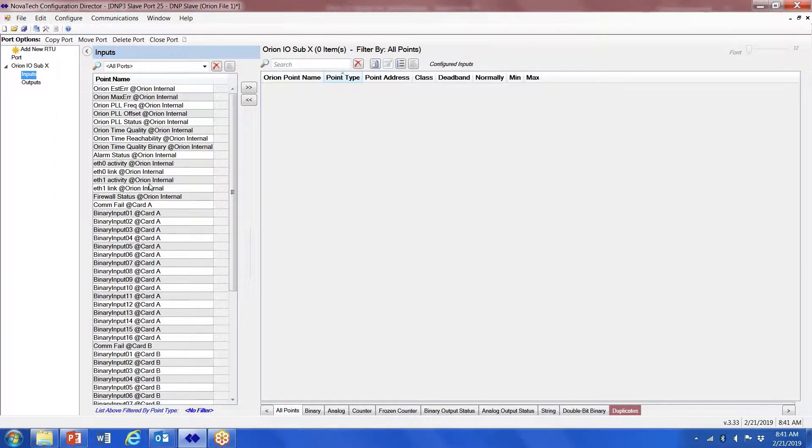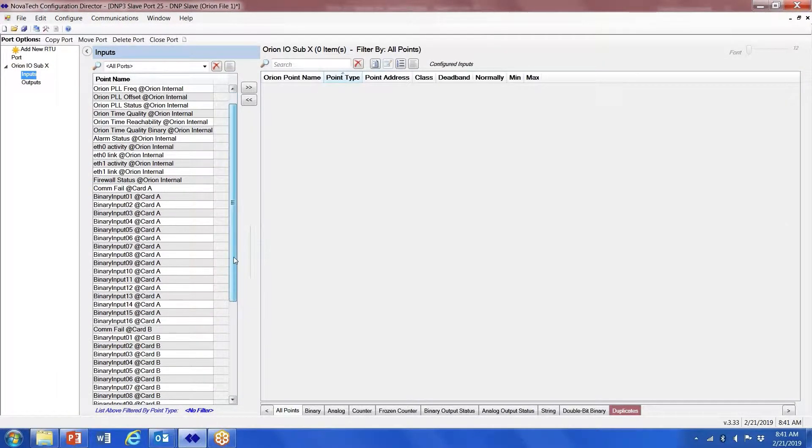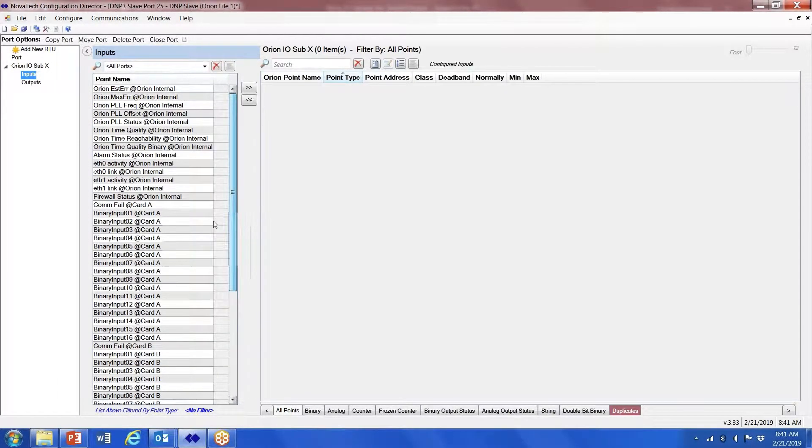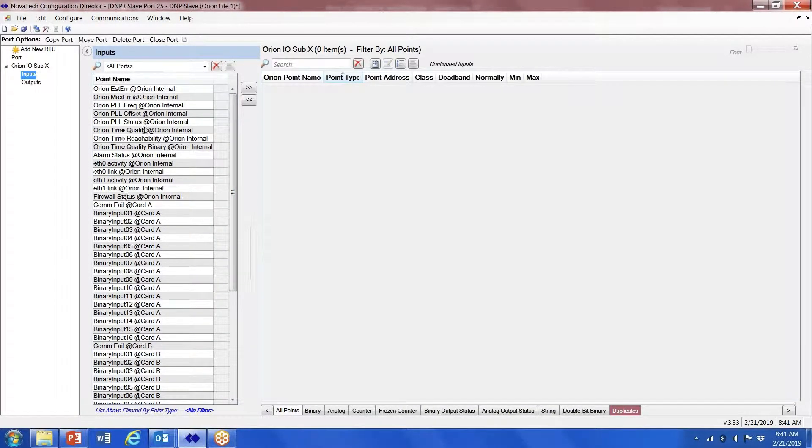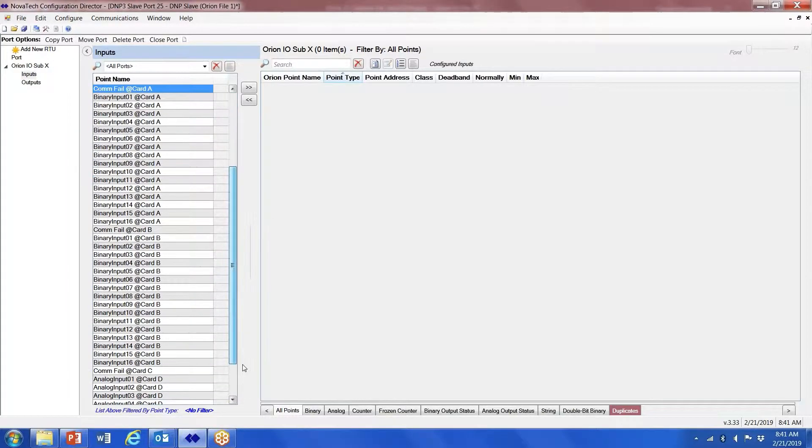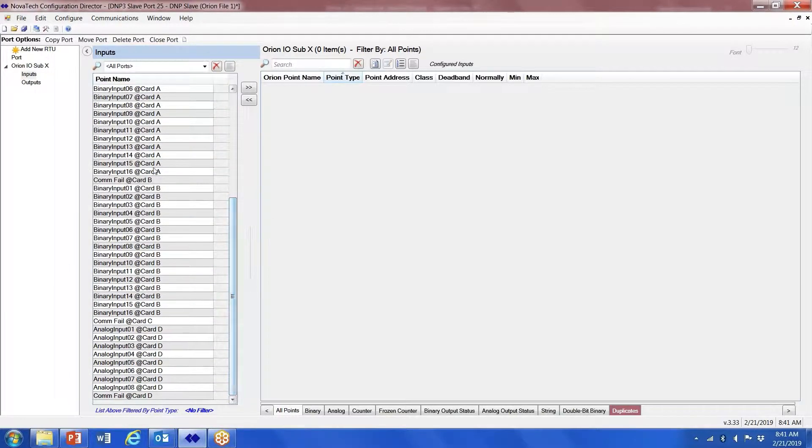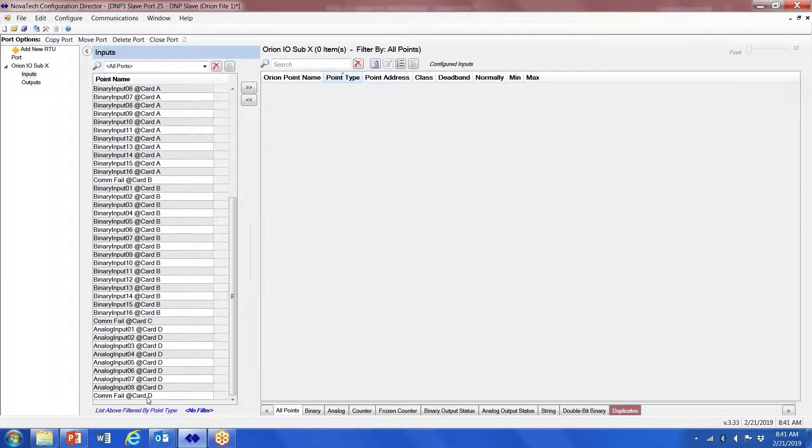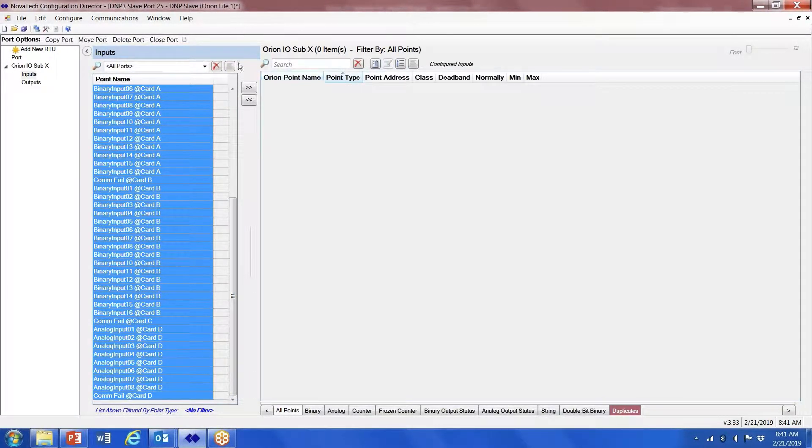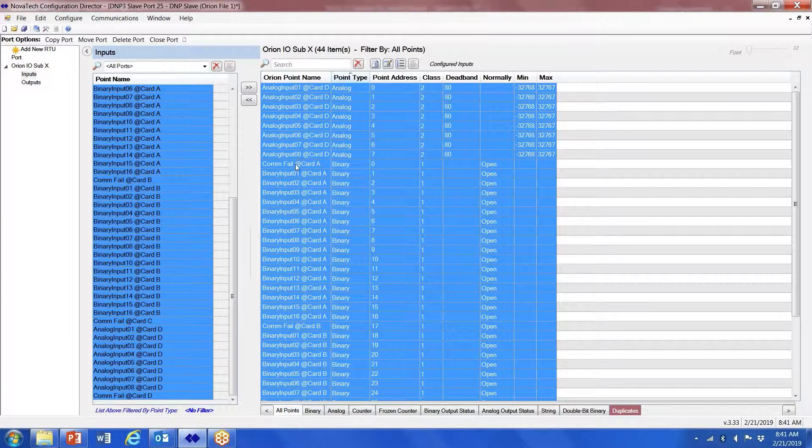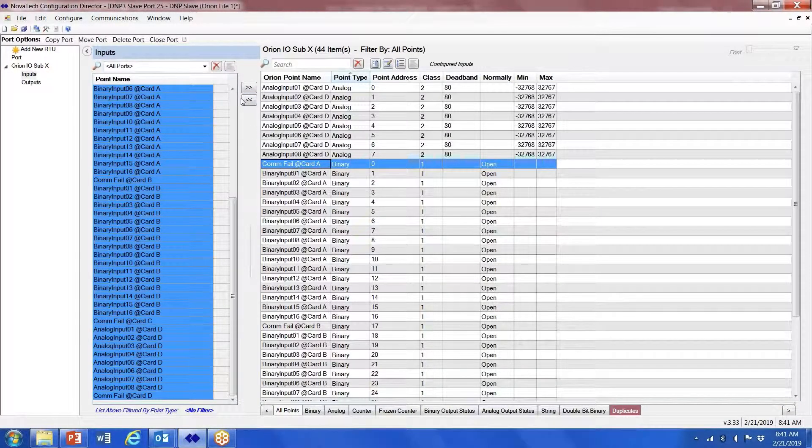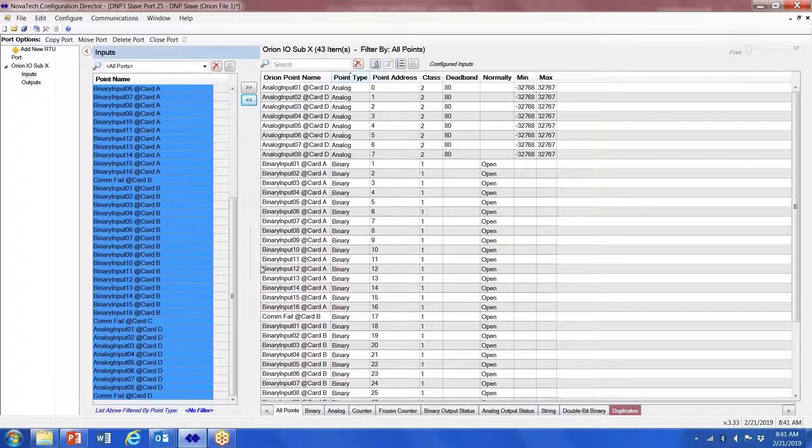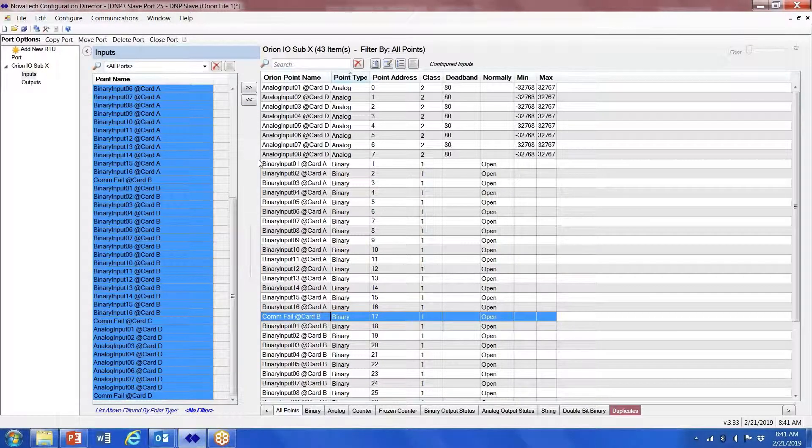Now here's my points list for all of the cards that I've configured. Notice you get all of this information that you get with a typical Orion RTU, but we also get a Comm Fail bit for each one of the cards. Not everybody likes to map that over, but you certainly can if you want. Grab all the points, map them over, and if you choose not to do comfails, just map those back.